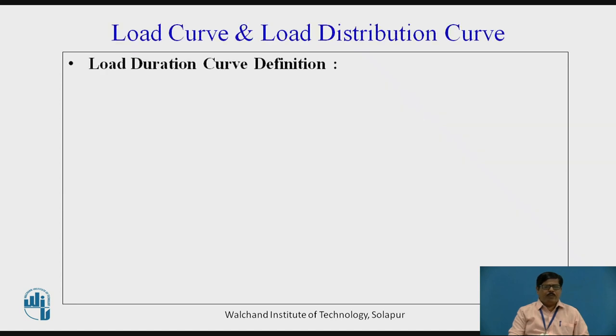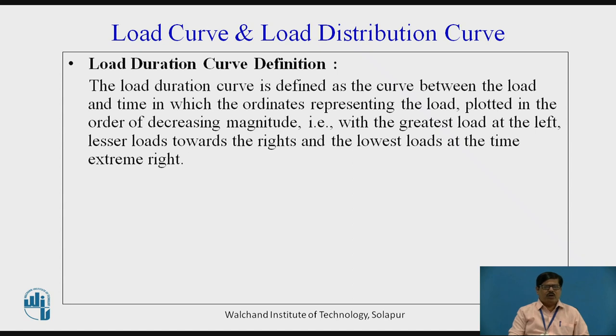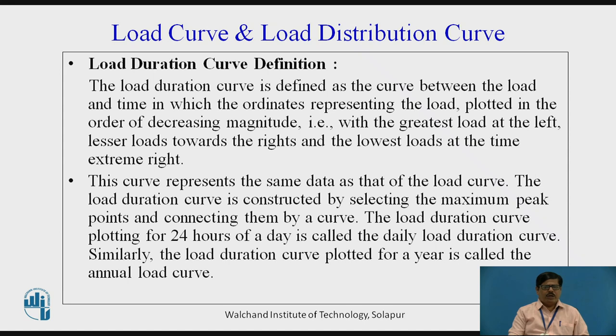Now, let us see what do we mean by Load Duration Curve. Load Duration Curve is defined as the curve between load and time in which ordinates representing the load are plotted in the order of decreasing magnitude. We take the time and plot the load with the greatest load at the left and lesser loads towards the right and lowest loads at the extreme right. Thus, the Load Duration Curve represents the same data as the Load Curve, but the only difference is that the time is not taken in chronological sequence. The load duration curve is constructed by selecting the maximum peak points and connecting them by a curve. The Load Duration Curve plotted for 24 hours of a day is called the Daily Load Duration Curve, and if plotted for a year, it is called the Annual Load Duration Curve.